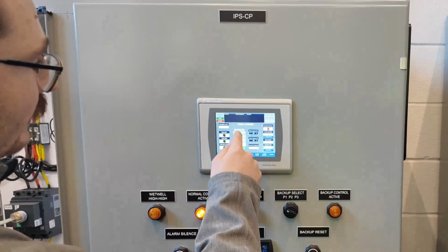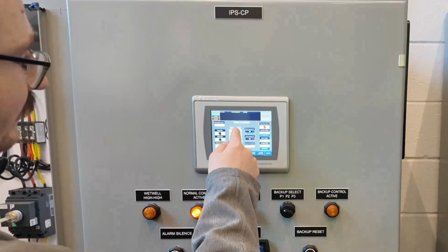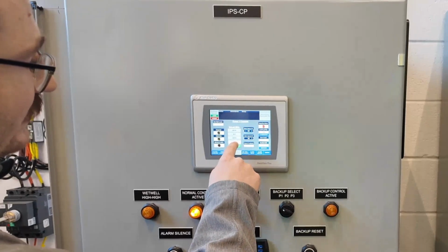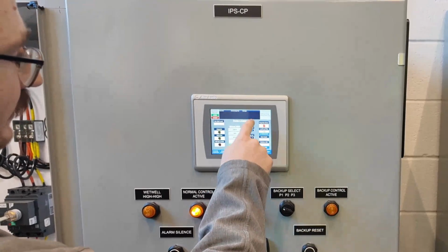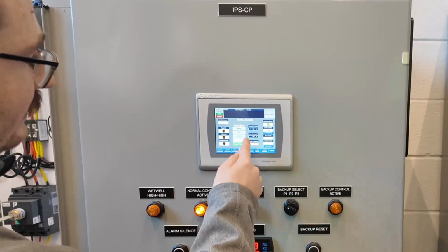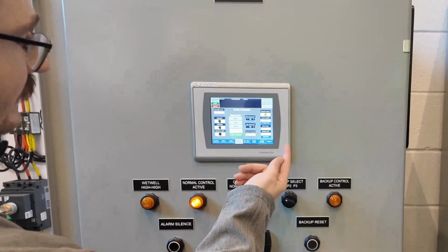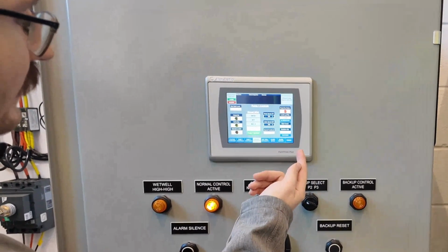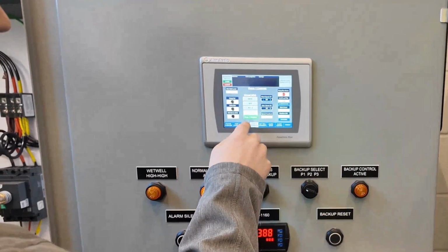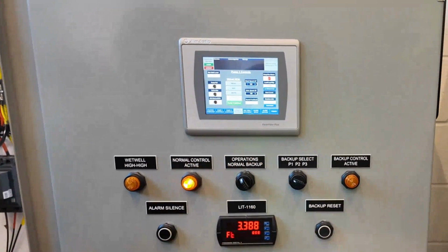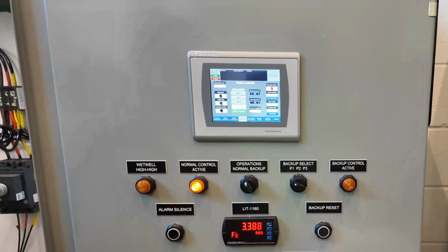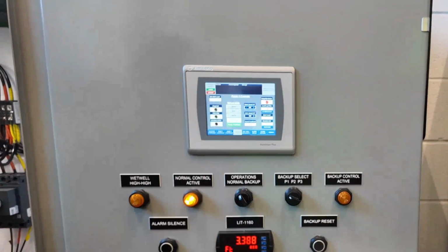So now you have access to your virtual HOA. It's going to give you an indication of what position it's in. So right now it's in the off position, so I'm going to change it to hand, it's going to run it, off is going to shut it off, auto's going to keep it in auto, and then it also is going to pop up with the pump enable/disable selector switch, so in case you ever want to just disable a pump and you don't ever want it to start, you can disable it.